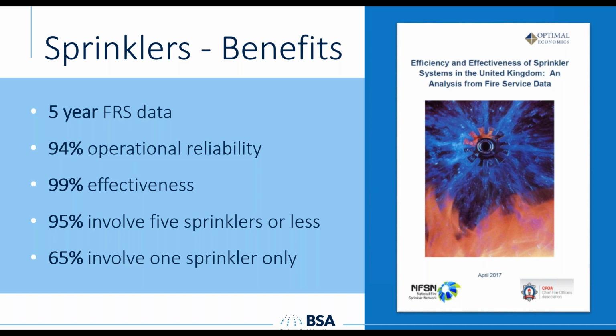The thing I'd point to in these figures is that these are real fire events, not a statistical exercise where somebody worked out theoretical probabilities. What they show is that the notion that all sprinklers go off at once is rubbish, as demonstrated by the number of heads that operate in individual fires. It also shows a high level of effectiveness, which is why you see calls from the fire service that we should use more sprinklers in fire situations.